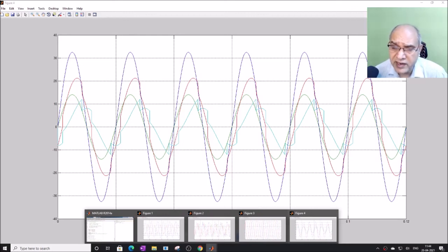So there is no net active power involved with the compensator, but each phase of the compensator may handle active power. That's why they call it an active power filter. They have this capacity. Because of this capacity, we can compensate any kind of load, 3 phase 3 wire, 3 phase 4 wire, any kind of variation which is possible with the different kinds of loads can be handled with these active power compensating schemes.